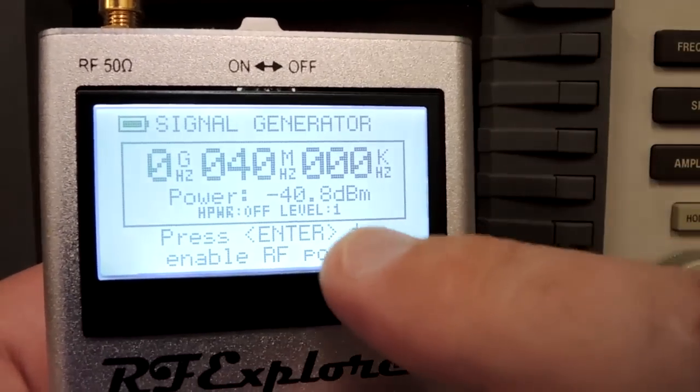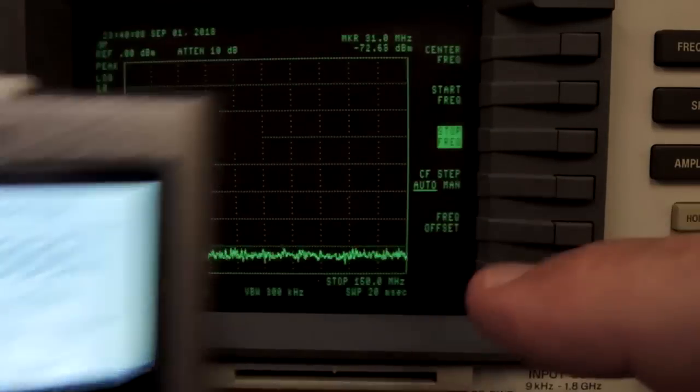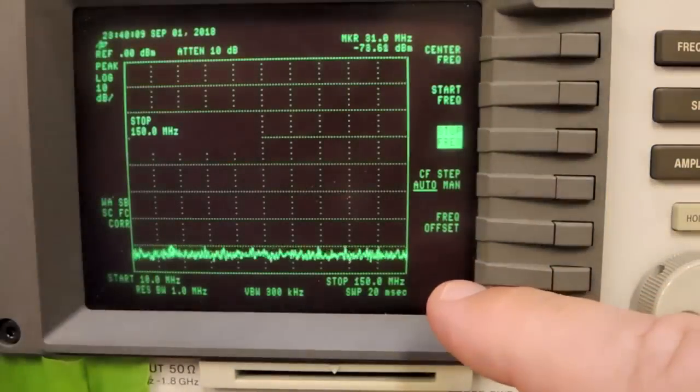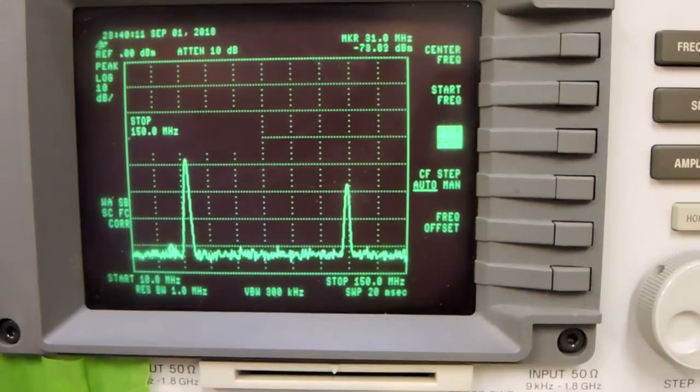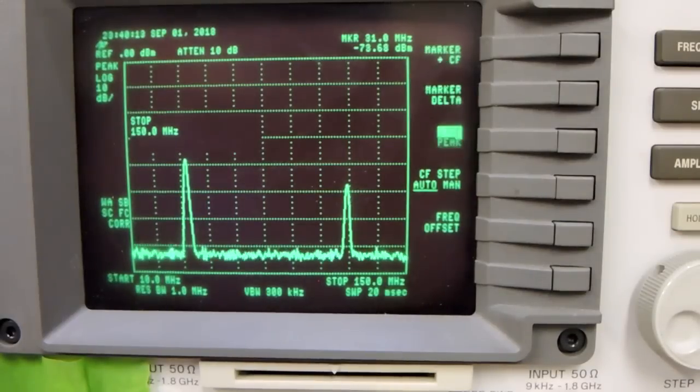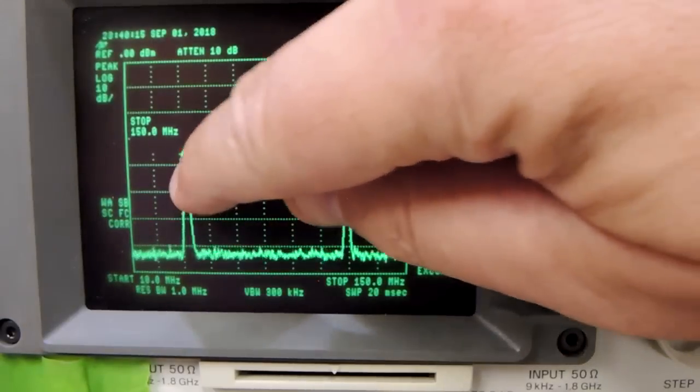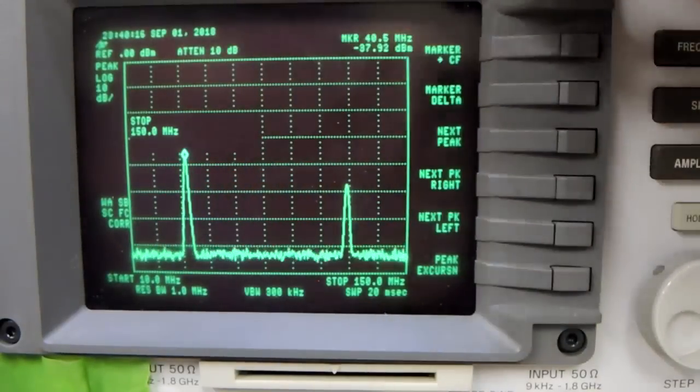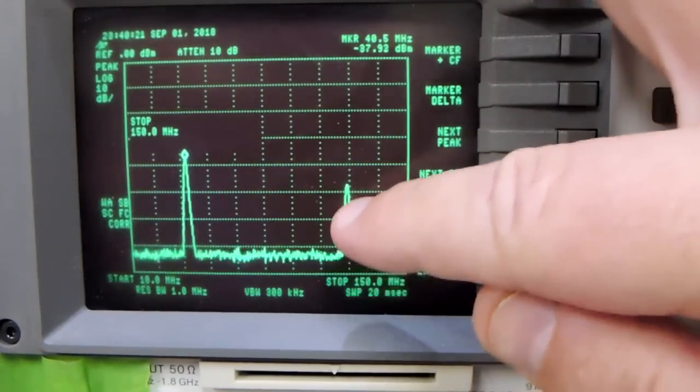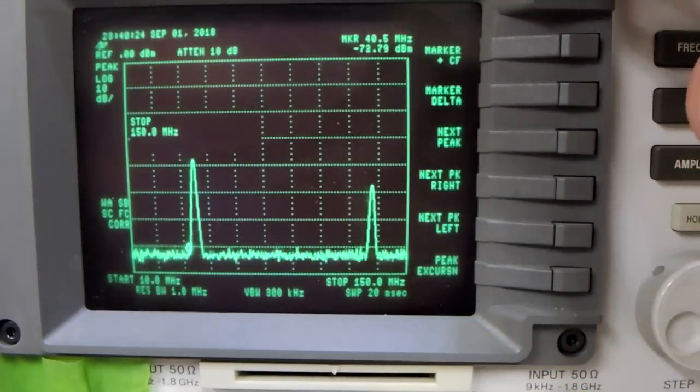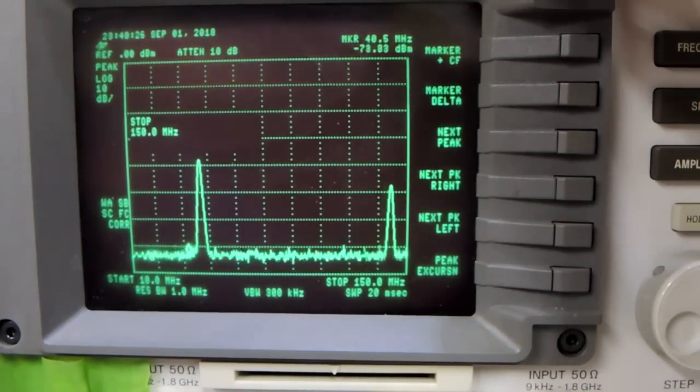So I set the generator to generate a 40 MHz signal and connected it to a spectrum analyzer. Let's turn it on and do a peak search. Sure enough, this is coming at 40 MHz, which is just fine. Unfortunately, you can see a significant peak here. It looks like a harmonic. And it doesn't matter how much you increase or change the frequency. These harmonics seem to always be there.